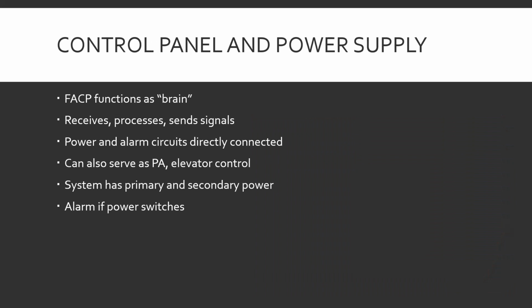Control panel and power supply. The fire alarm control panel functions as the brain of the fire alarm system. It receives, processes, and signals. What signals? Fire alarm pull stations, smoke detectors, rate of rise detectors. Smarter ones sense, hey, I've got a sprinkler head that's broken and flowing water. It takes all that information, processes it, and sounds alarms, sets off the flashing strobes and buzzers, and sends alarm signals to whoever's receiving the alarm from the system. Power and alarm circuits are directly connected into the brain. Obviously, everything has to come together: power for the system, the alarm systems through the building, detector systems, that kind of thing.